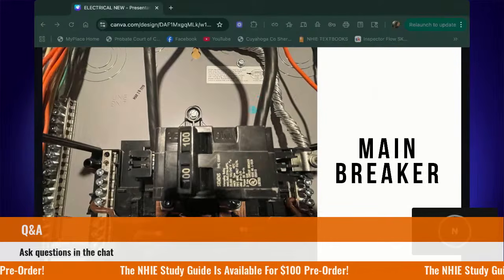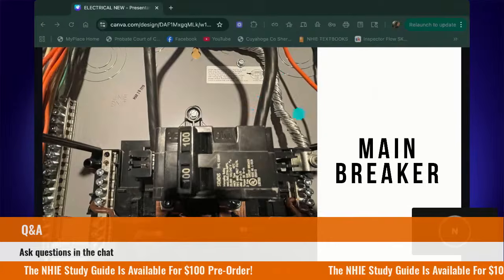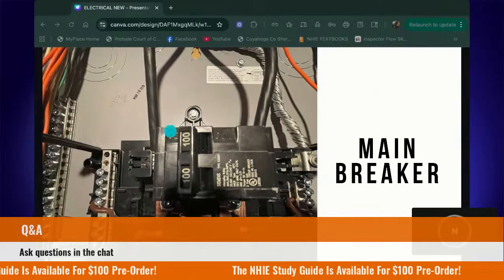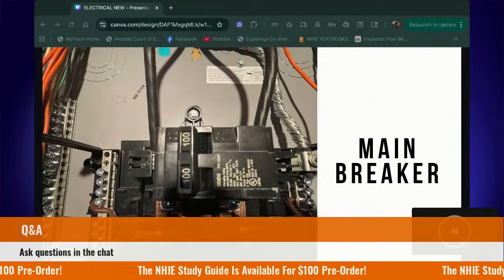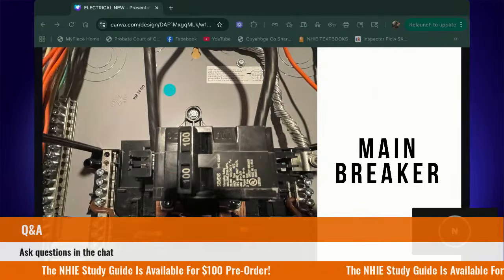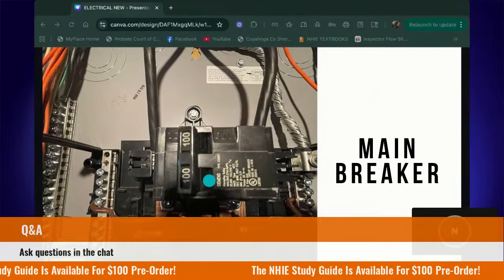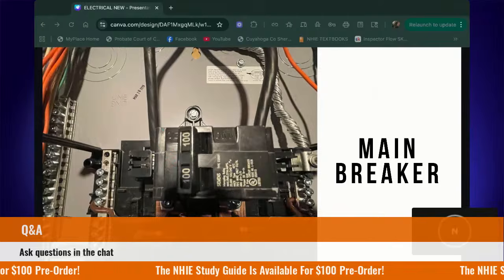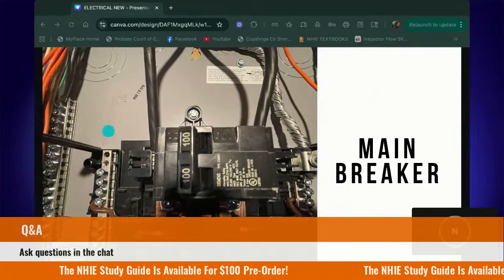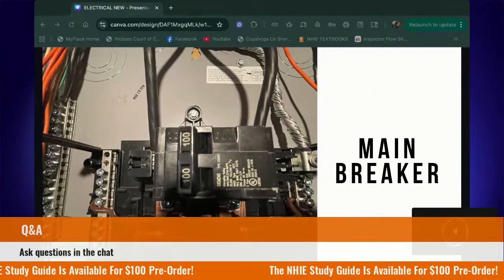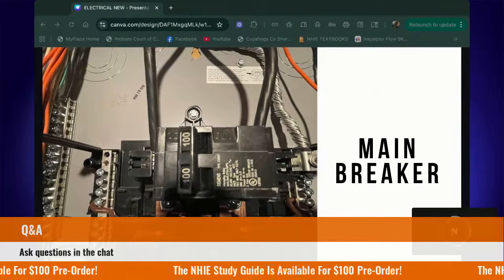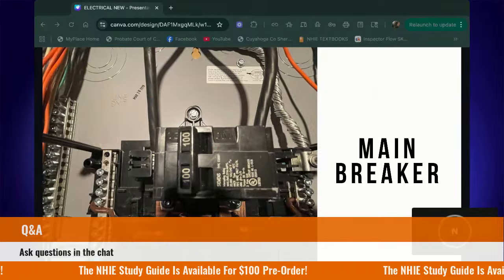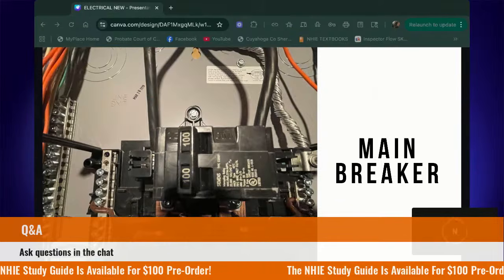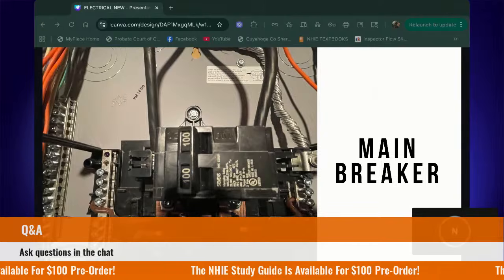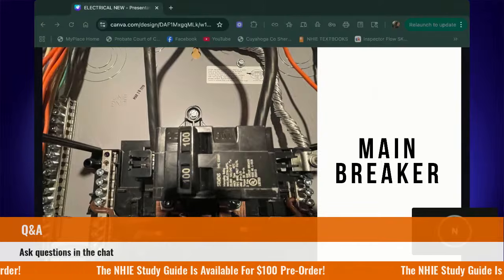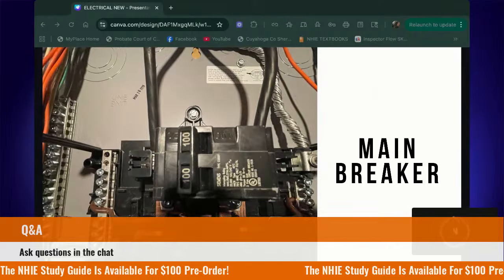But you do have to remember that the incoming service conductors are still energized. Remember, because they're getting their power from the transformer. If you cut this, yeah, you are stopping the power for the branch circuits, but these conductors will still be energized. Okay. In most panels, this main breaker will be at the top. However, it could end up being at the bottom. Sometimes we have DIYs and all that kind of stuff. It could be at the bottom.